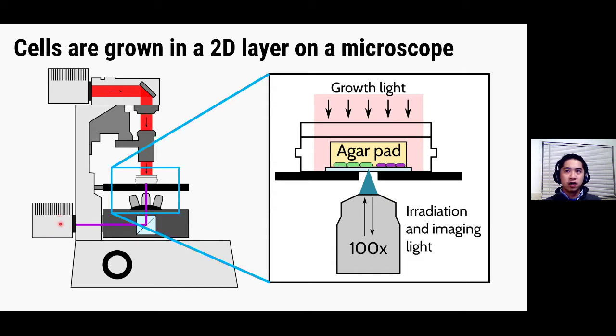And this lamp at the bottom here is much more intense and is focused through the objective lens onto the sample to excite fluorescence. And then the emitted fluorescence travels back through this objective and back through the same path and gets imaged onto a camera.